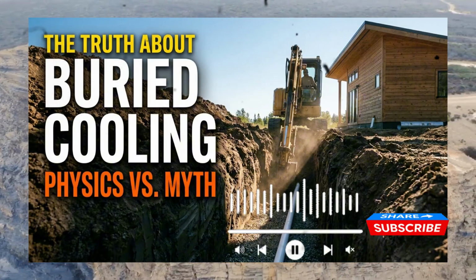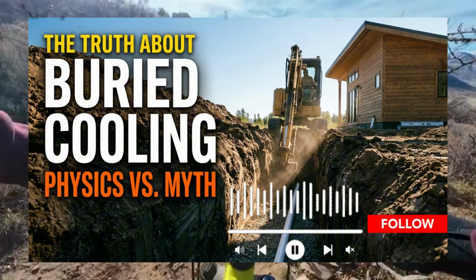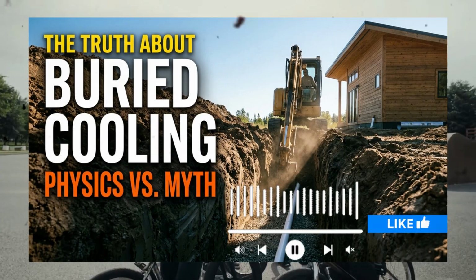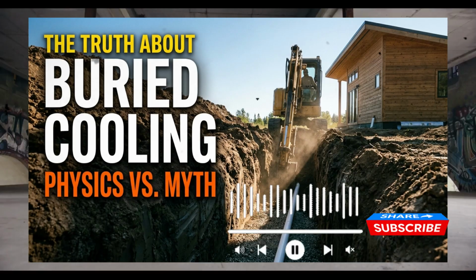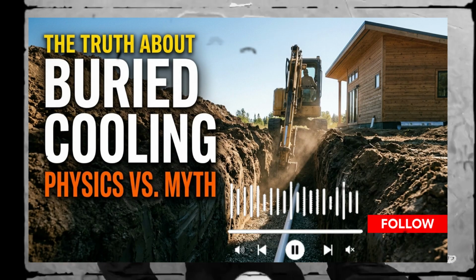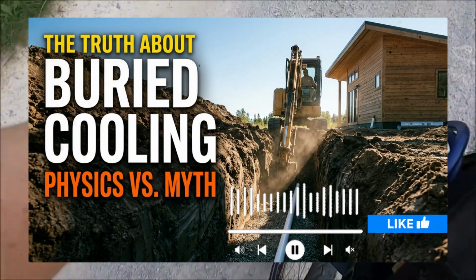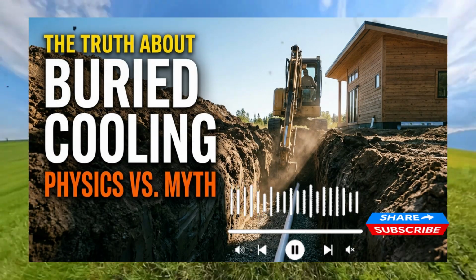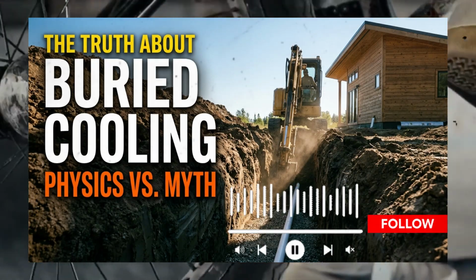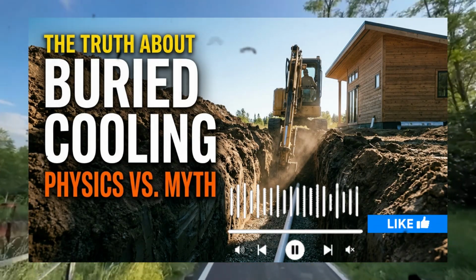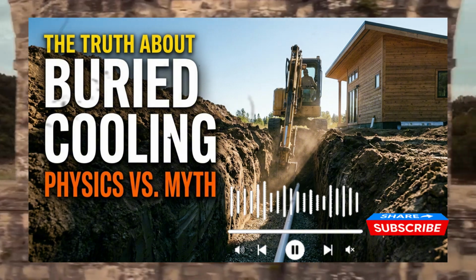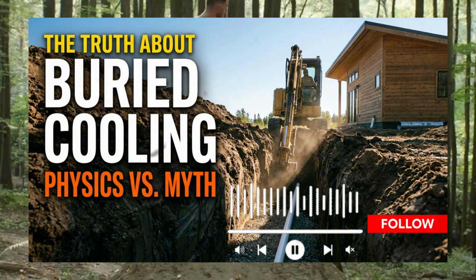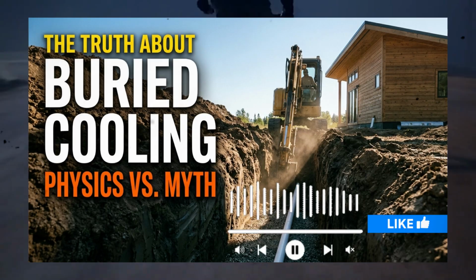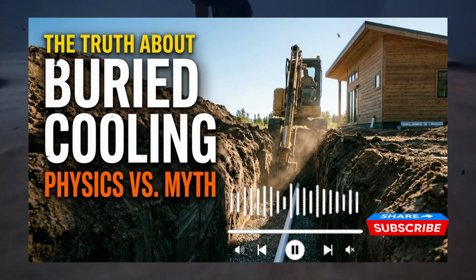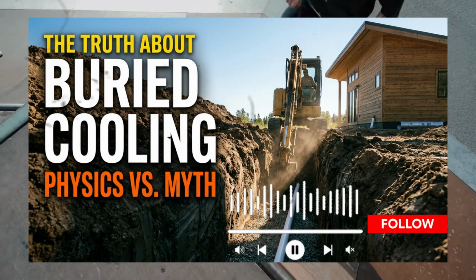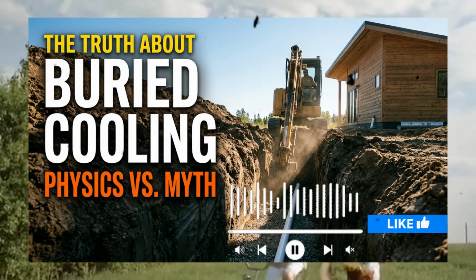A sharp 90-degree turn creates massive air turbulence. The air molecules slam into the outer wall of the bend, creating a high-pressure zone that acts like a physical wall, choking the flow and causing a major drop in static pressure. We resolve this by using only sweep bends, gentle 45-degree couplings separated by straight runs of pipe. By using two 45-degree bends with a short straight section between them, we allowed the moving air to transition smoothly around corners without losing its momentum.